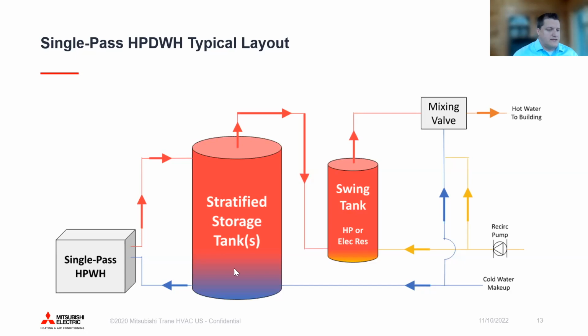So you'll see while we have the same main storage tank here, we also have an addition of what we'll call a swing tank or a maintenance tank. And really what this is to do is to eliminate your recirc water coming back to the system and mixing up your stratification in the main tanks. There's a misconception out there sometimes that the swing tank is for backup heat or other things like that. It really isn't the purpose.